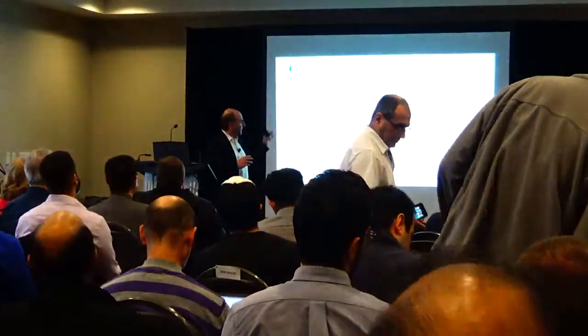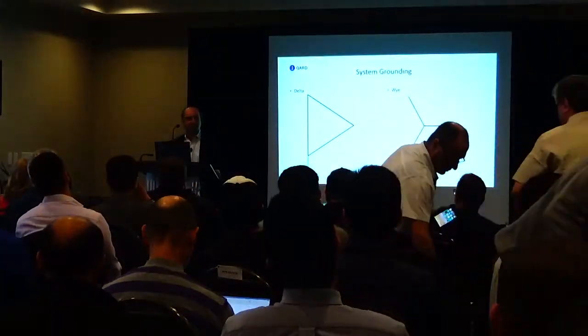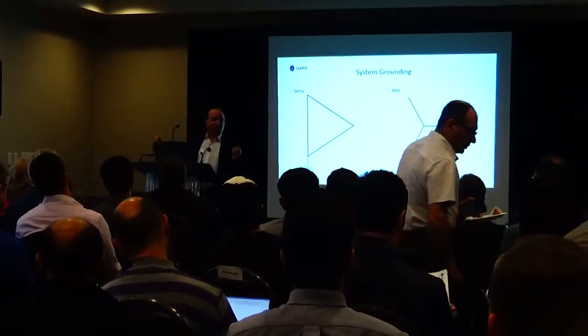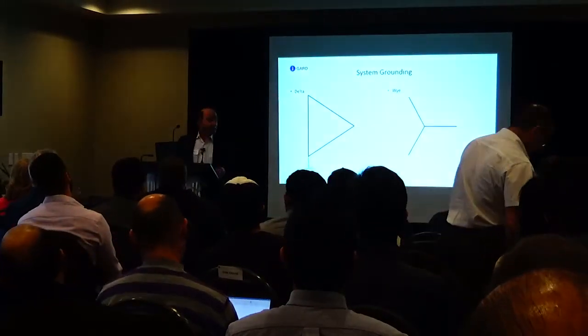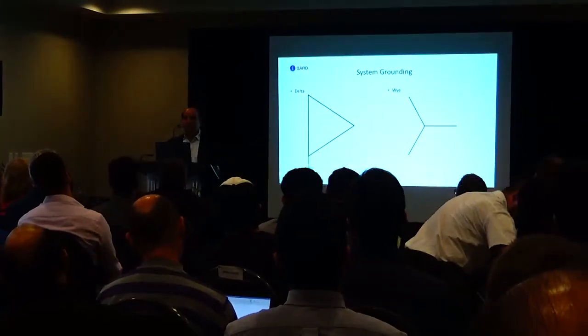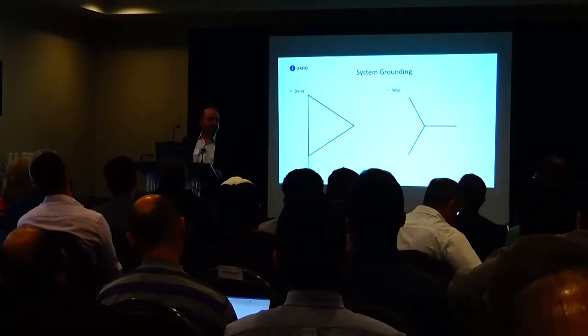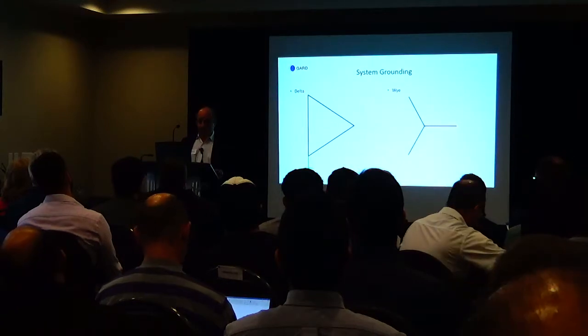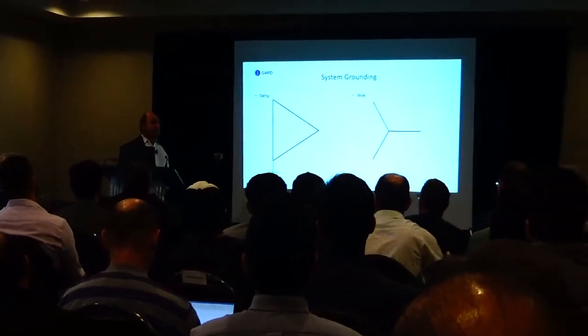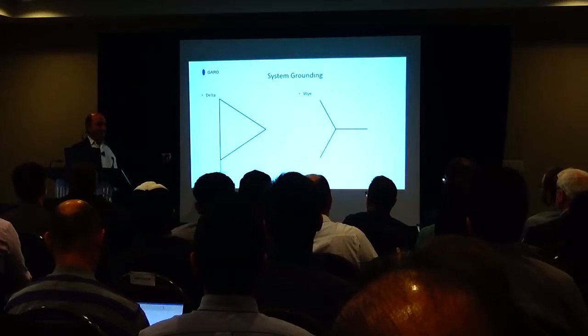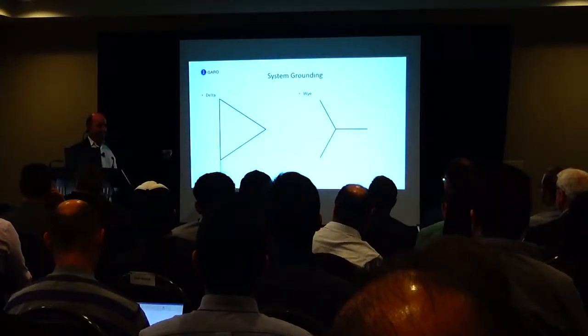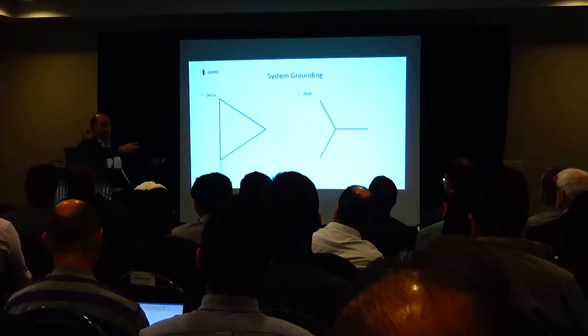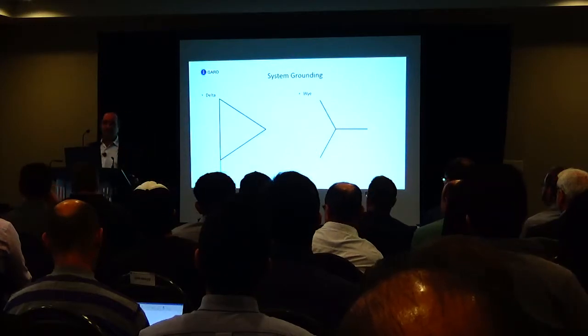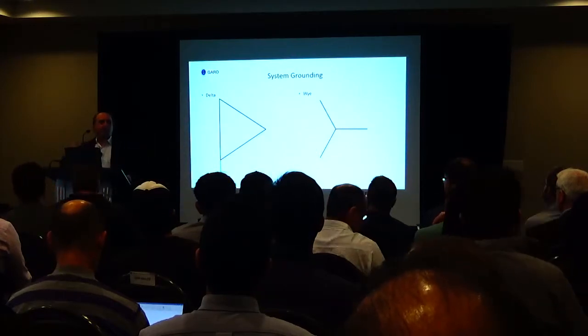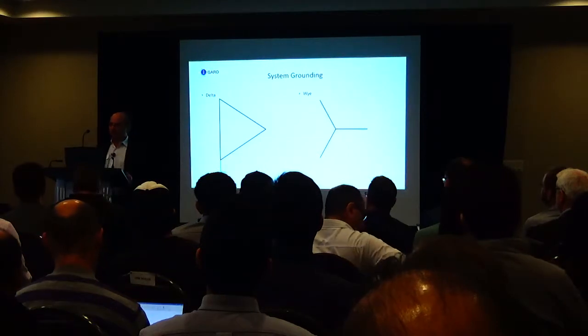Nobody. All right, so if you're in the electrical field and you see a delta system and you're measuring phase to phase and phase to ground, and you measure 600 volts phase to phase, 600 volts phase to ground on two phases, and 0 volts to ground on the third phase. What do you think you have? You have a corner grounded delta system, right? According to this scheme, right? You could have a ground fault if there was no ground in the system. So that's why I'm saying qualified people need to understand what's going on.